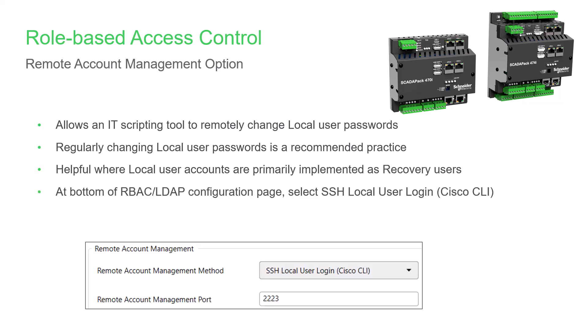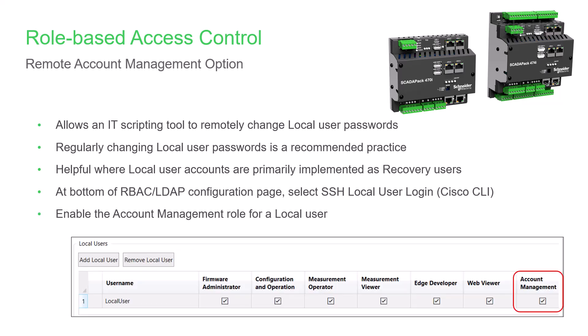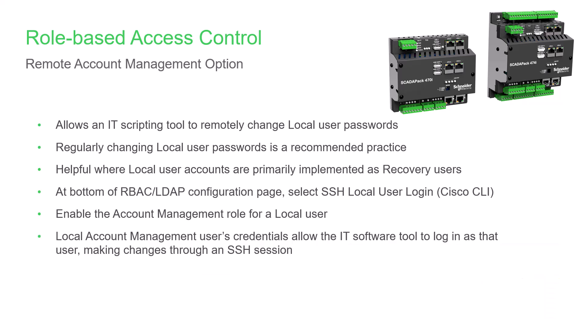You enable Remote Account Management by selecting RBAC LDAP on the Configuration tab. Scroll to the bottom of the page and select SSH Local User Login. To use this service, enable the Account Management role for a local user. The local account management user's credentials will then be used by the IT software tool to log into the SCADAPack and make changes through an SSH connection.